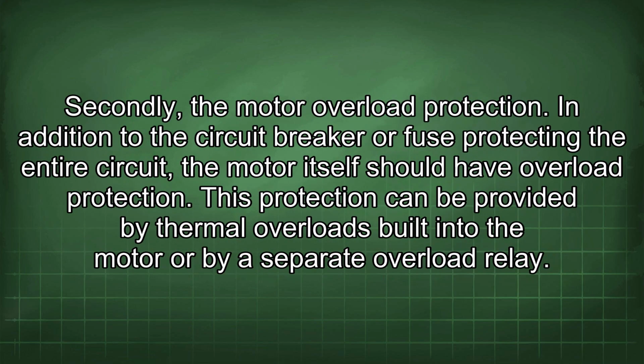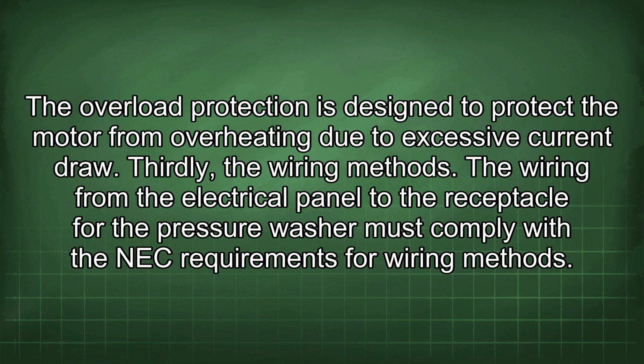Secondly, the motor overload protection. In addition to the circuit breaker or fuse protecting the entire circuit, the motor itself should have overload protection. This protection can be provided by thermal overloads built into the motor or by a separate overload relay. The overload protection is designed to protect the motor from overheating due to excessive current draw.